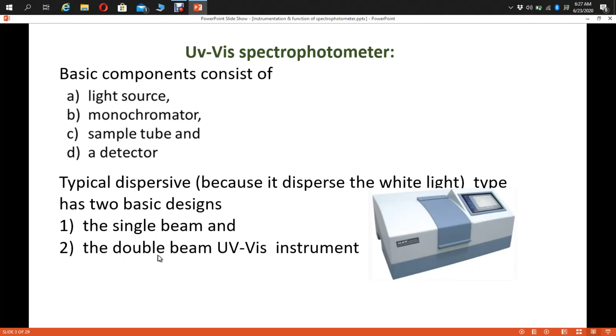The first part of the spectrophotometer consists of the light source. There are two light sources, the deuterium lamp and the tungsten lamp. Light from the light source comes to the collimating convex lenses and passes through the monochromator. After the monochromator, in a single beam spectrophotometer, it passes through the cuvette or sample tube, and from the cuvette it passes directly to the detector, that is a photocell, and from the photocell it goes to the readout device, that is the galvanometer.